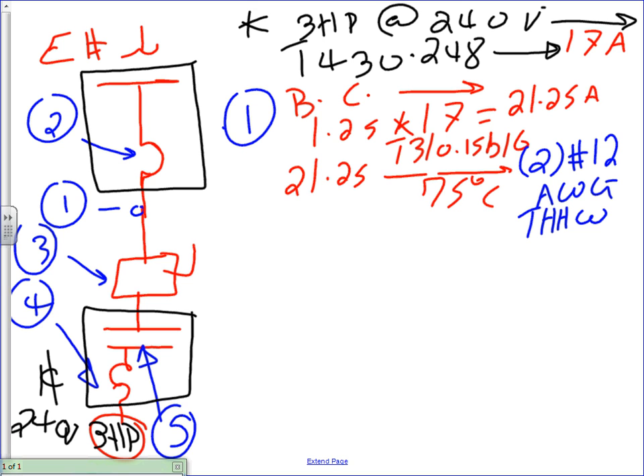Remember that when we went through the whole 310.15(B)(16), we said motors are an exception. They're all defaulted, the terminals on them are 75 and we rate them per 75, right? Defaulted to 75, when we did that code worksheet, we had different terminals. If you don't know, for motors it is 75. Okay, so that's number 1. Any question, guys, about number 1? All right, let's go to 2.